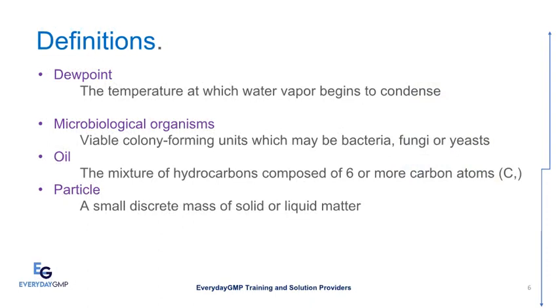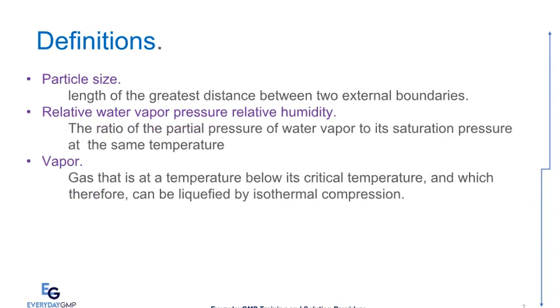Some definitions: Dew point — the temperature at which water vapor begins to condense. Microbiological organisms — viable colony forming units, which may be bacteria, fungi, or yeasts. Oil — a mixture of hydrocarbons composed of six or more carbon atoms. Particle — a small discrete mass of solid or liquid matter. Particle size — the length of the greatest distance between two external boundaries. Relative water vapor pressure (relative humidity) — the ratio of the partial pressure of water vapor to its saturation pressure at the same temperature. Vapor — a gas that is at a temperature below its critical temperature and which, therefore, can be liquefied by isothermal compression.